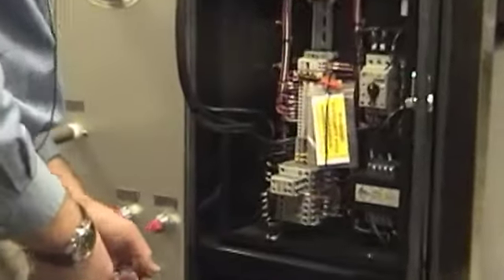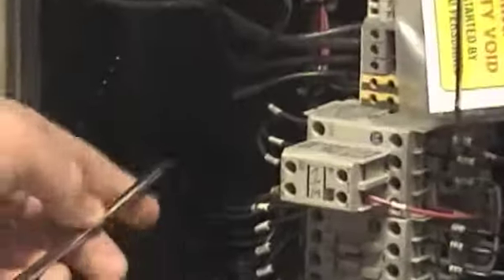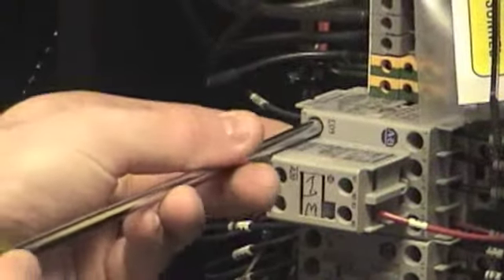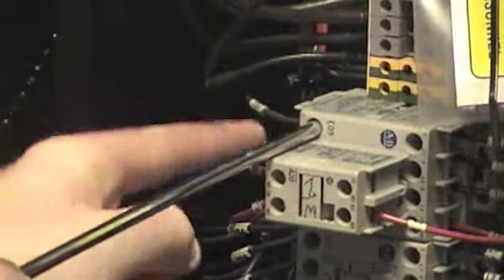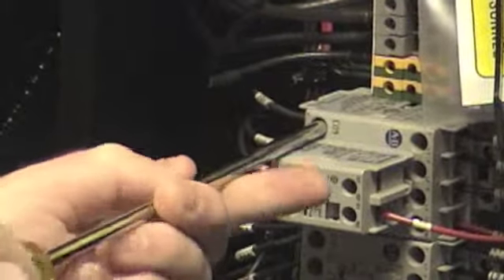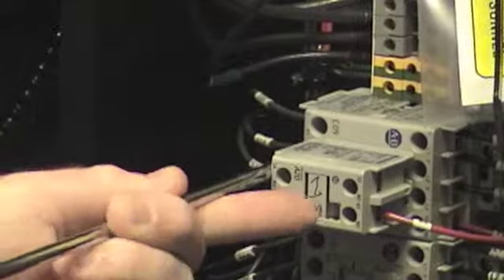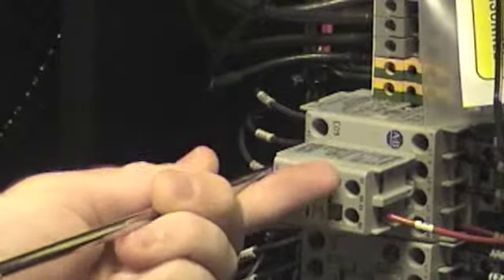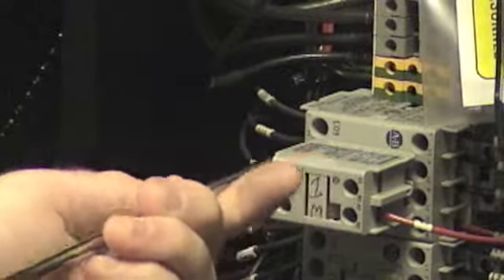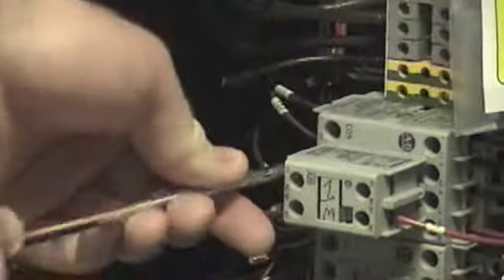First of all, obviously make sure you shut off your main power disconnect on the wall or at your location, and then we're going to switch 2 of these legs around. These 3 legs are the ones for the pump, so if we switch 2 that are next to each other, it should reverse the rotation. So once we're done there, we've switched these 2 leads for the pump. We can test it and make sure that the rotation is good.